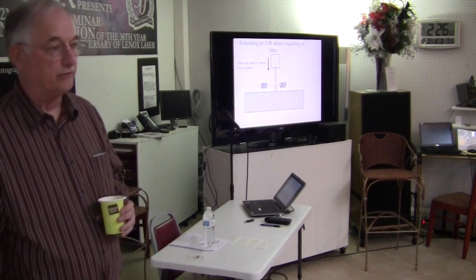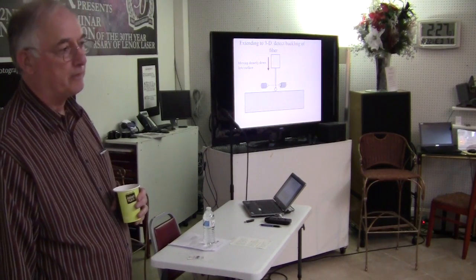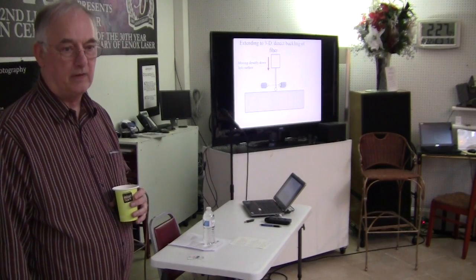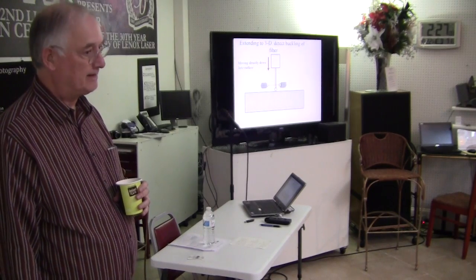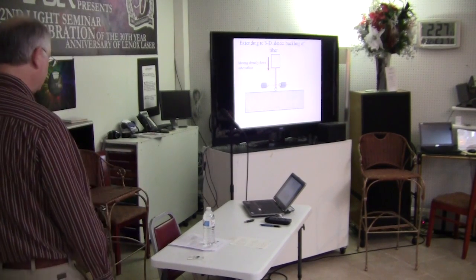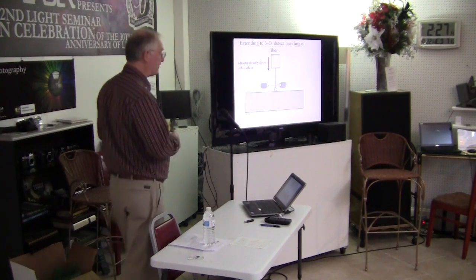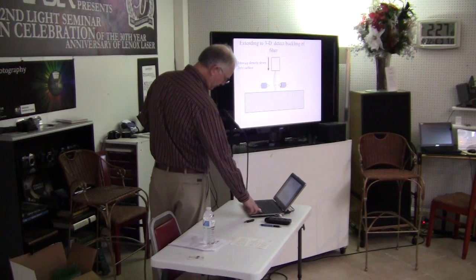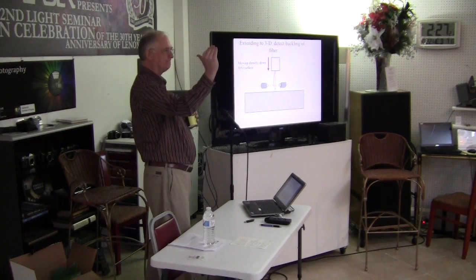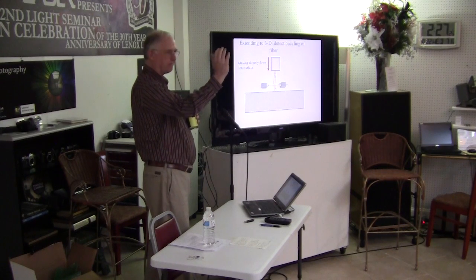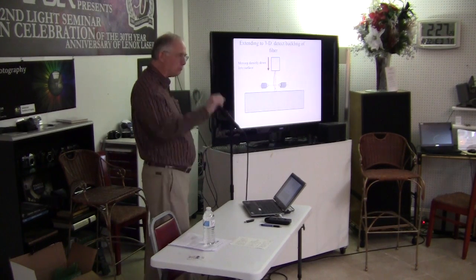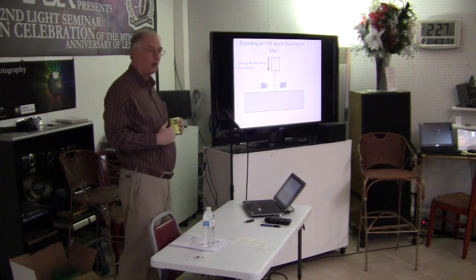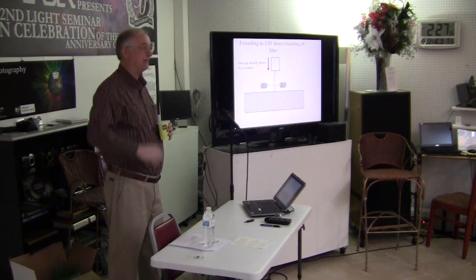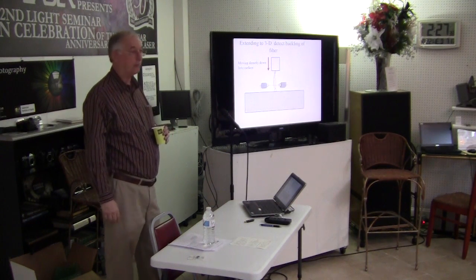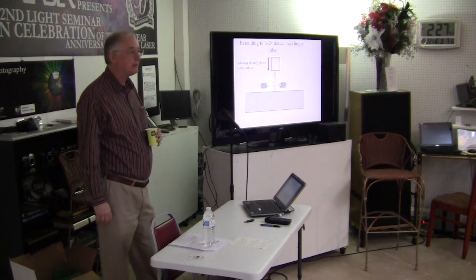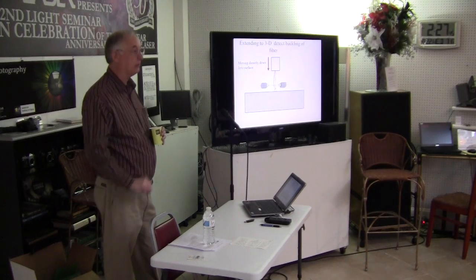We're busily making Model 3 of the probe that doesn't use a glass fiber, it uses a metal fiber. And so the insides are a bit different. Because glass is hard to make round. Now, to do Z is actually quite easy. The fiber is so thin that when you come straight down into something, it goes boink in milliseconds. It basically pops up. And so now you know you've hit something with really good sensitivity, even better sensitivity than X and Y. You actually see the sensitivities better in Z. And since these things are long and thin, they don't break, they just bend. Glass is extremely tough when it gets really, really small.